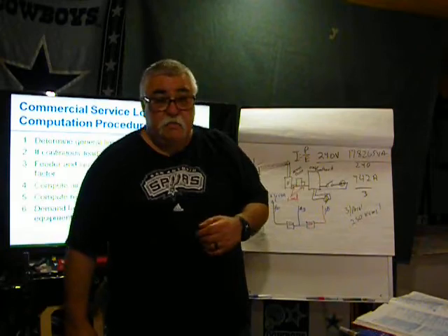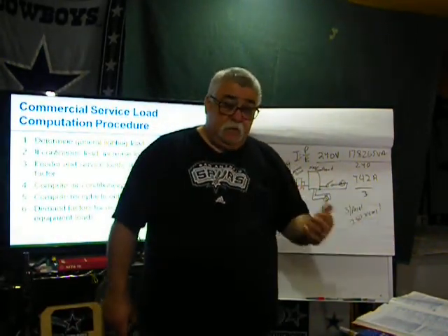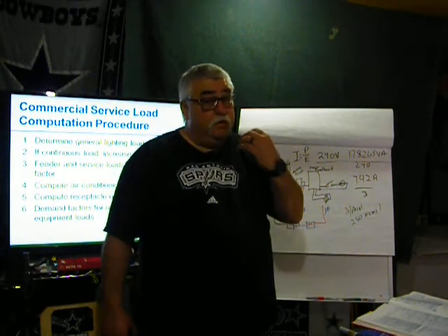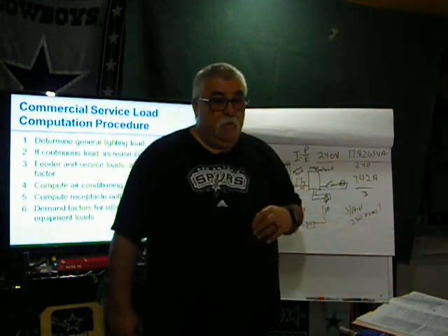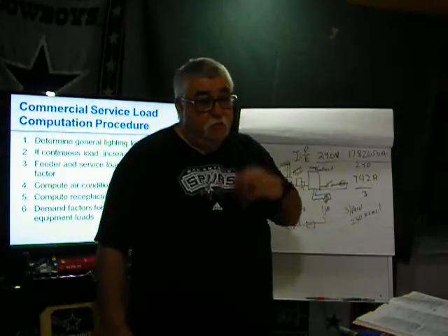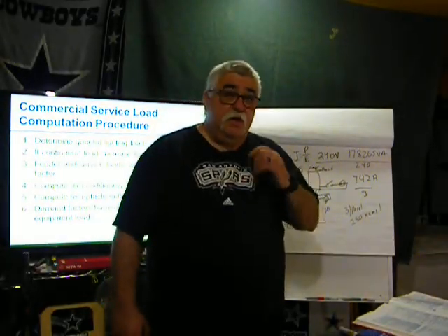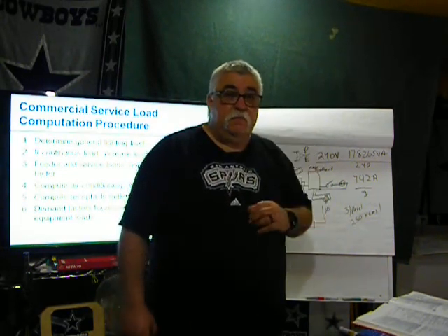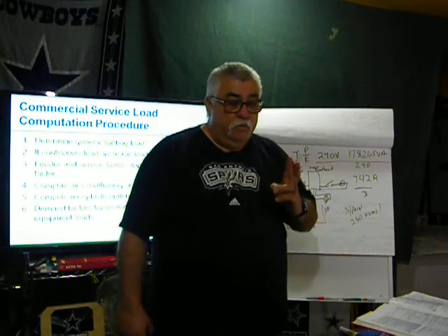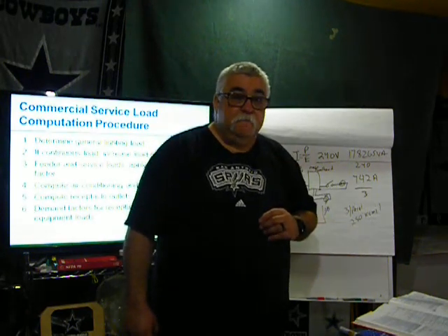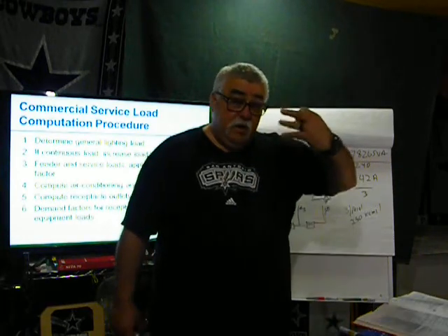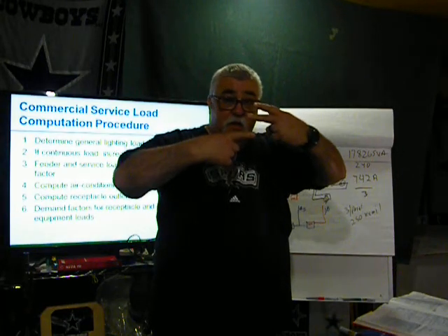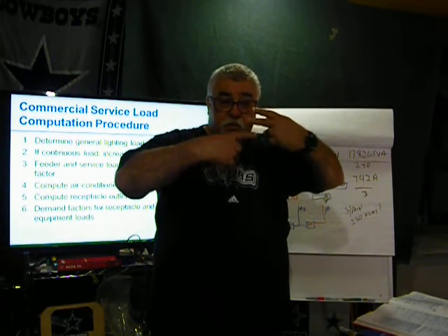So I want you to do the same thing, but I want you to turn around. Table 4, table 5, find me a wire size. So how many wires are you going to have in that conduit? 4. So your feeder size, remember, if your load is over 200 amps, you can size your neutral 70% less. So your neutral can be smaller, so that means that you're going to have 3 hots, and then a grounded wire or a neutral wire, which would be one size.